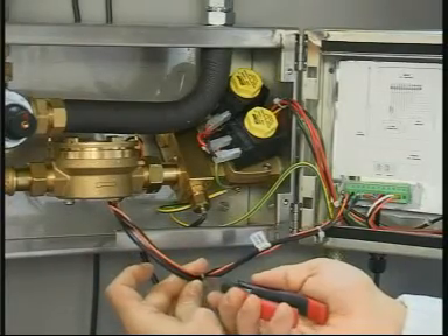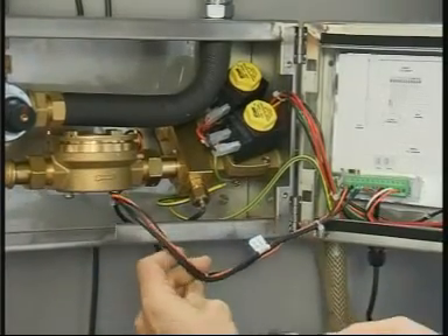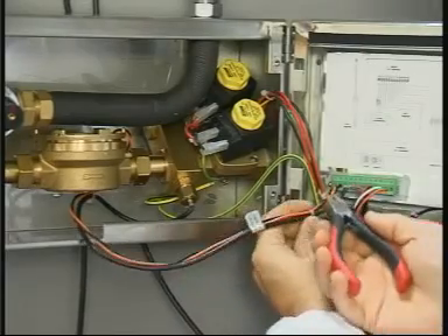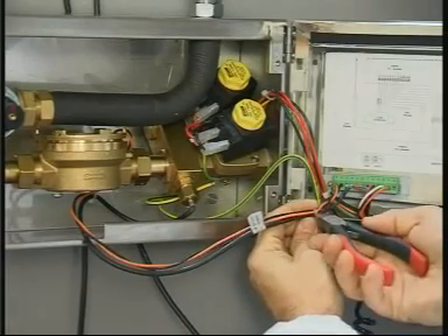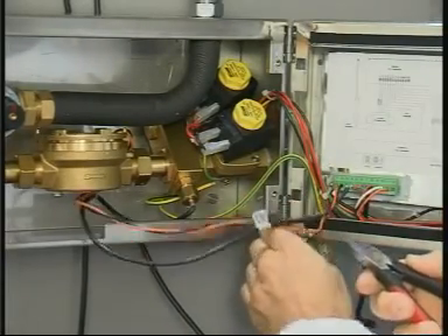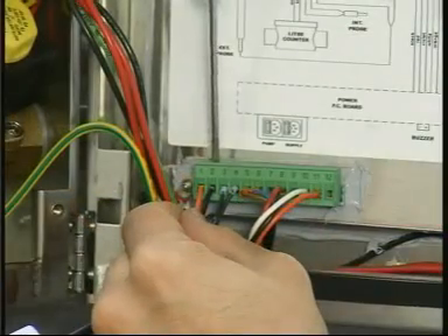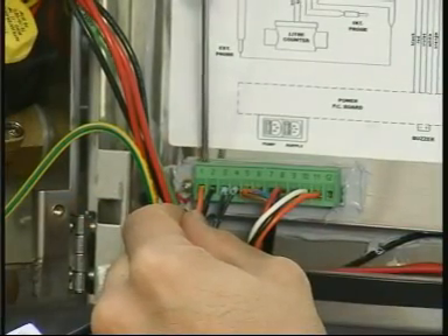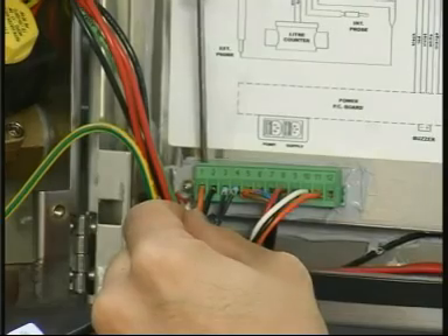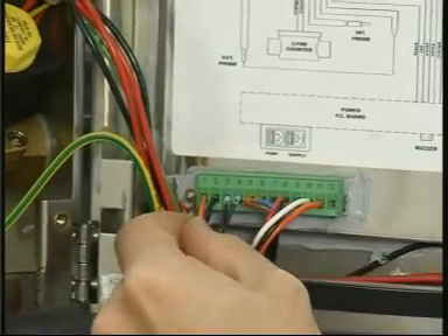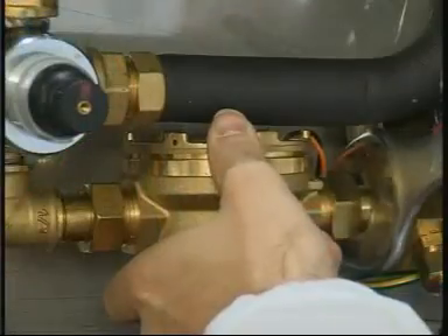Replacement of litre counter. Close the inlet ball gate valves and release the pressure. Switch off the supply to the machine. Separate the litre counter wires from the cable of the probe. Unscrew terminals 1 and 2 as shown.